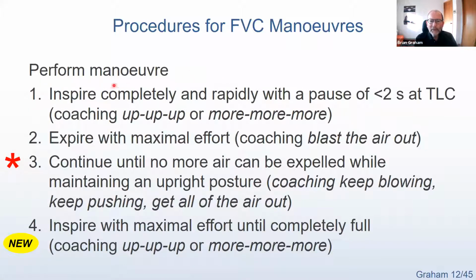So in performing the maneuver, in 2005, there were 3 main phases. Now there's 4. So the first phase is that first breath right up to the top with a pause of less than 2 seconds at TLC. And this is something we've really emphasized more in these guidelines, is coaching people to get to the top. We found that that's something that's just not happening nearly as well as it should be. And so do that extra coaching to get them up. Then there's the expire with the maximal effort, blasting the air out. And the third step is continuing until no more air can be expelled while maintaining an upright posture.